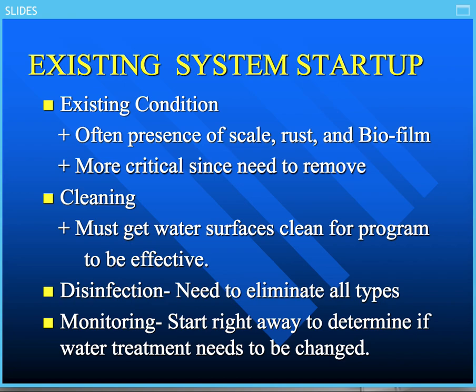So you've got to make sure that the existing system is devoid of scale and corrosion. Does that mean that the owner has to chemically clean it? The answer is yes. Does he want to do that often? No. So you have to be able to identify that there is a potential here. It's very critical, because if you don't remove this, you're going to get continuous corrosion and scale in your system, and biological problems. So it's very important that you get those water surfaces clean, and that is absolutely what we have to do to keep systems clean.